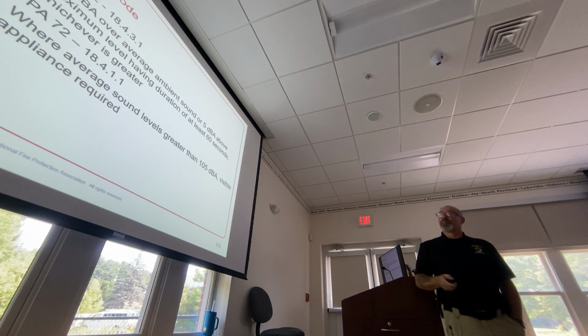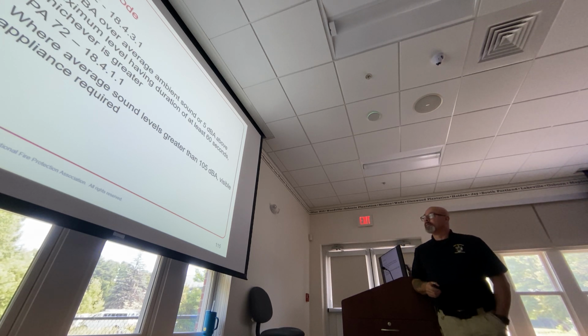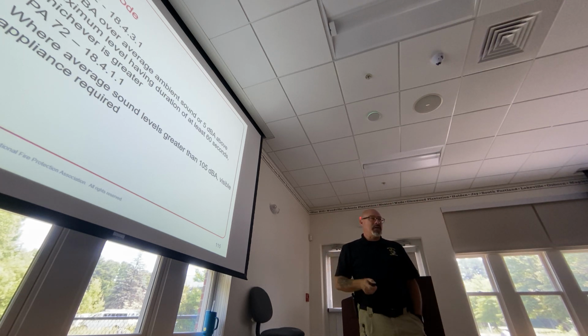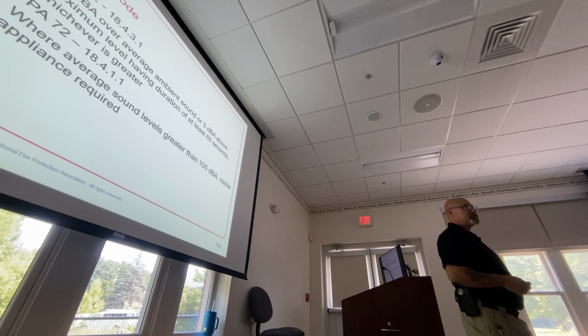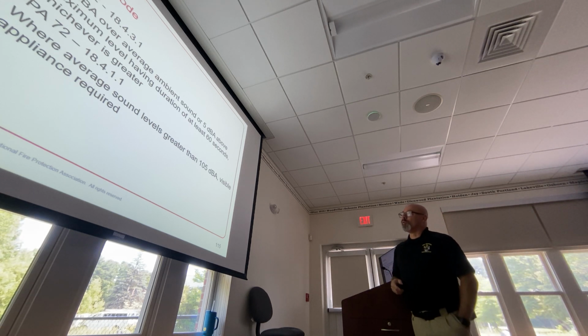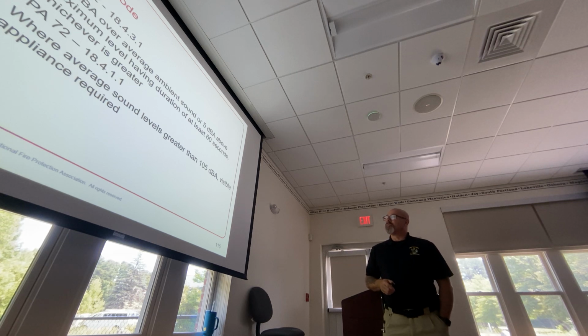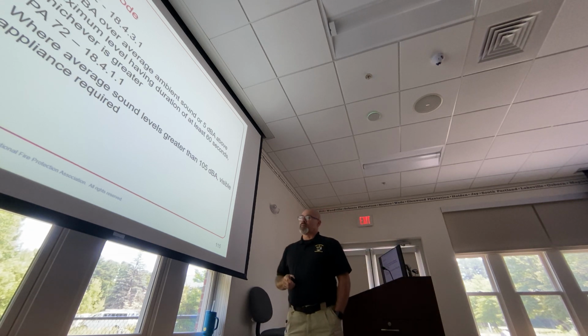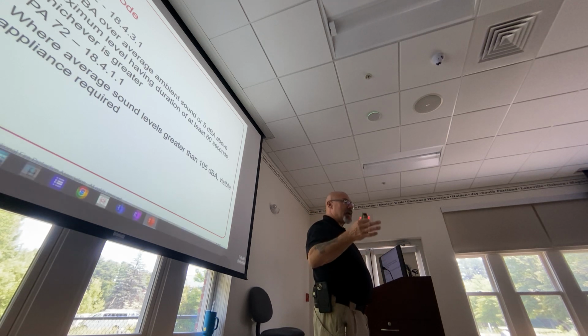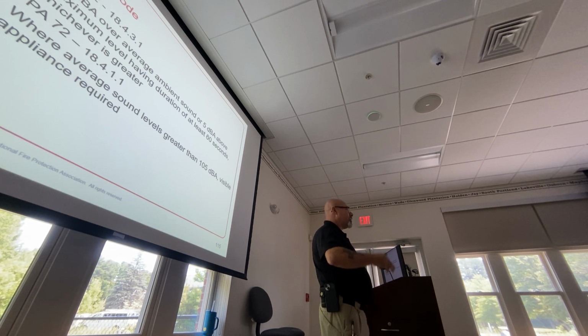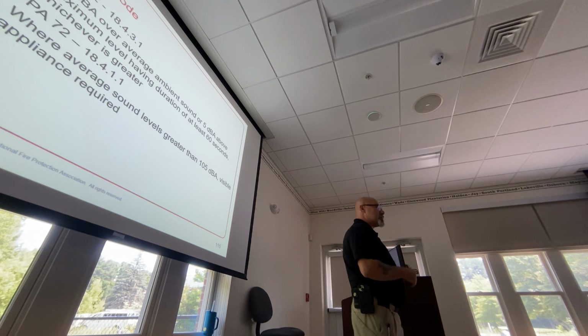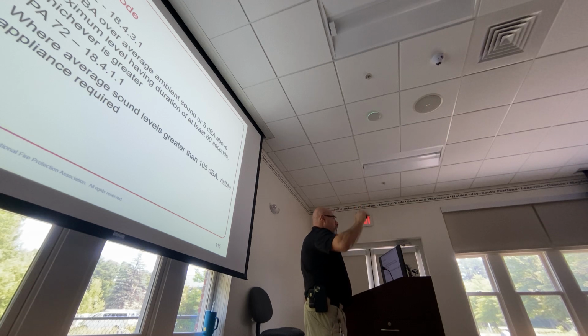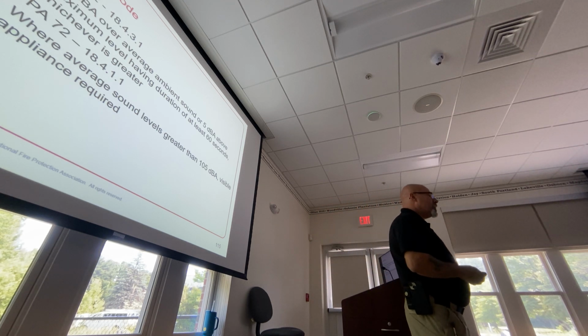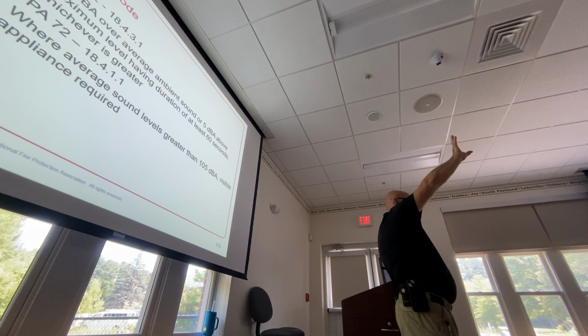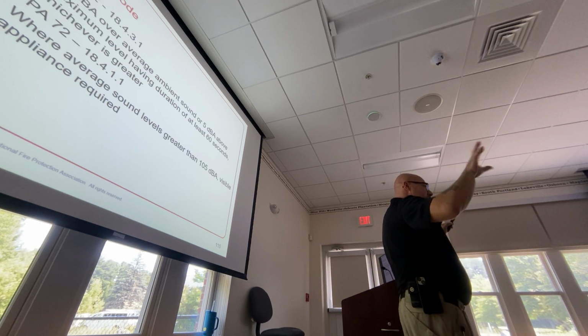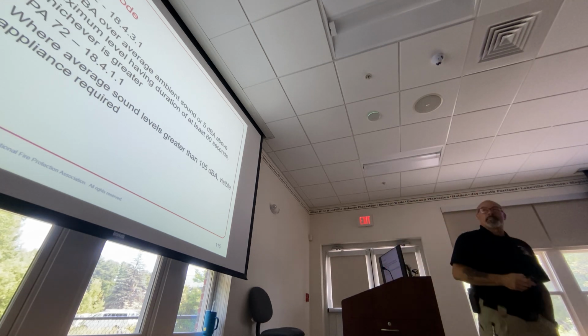So 18431 and 18411, because again, they're on the screen, probably places you should be tabbing and highlighting. 18411, where average sound levels are greater than 105 decibels, visible appliances are required. So go back to that factory or that industrial mode again. We have sounds that are greater than 105 decibels all the time. You have to have visible notification devices available. Typically, that's something that you're going to see up in the ceiling or up in the roof that's going to notify what's happening.